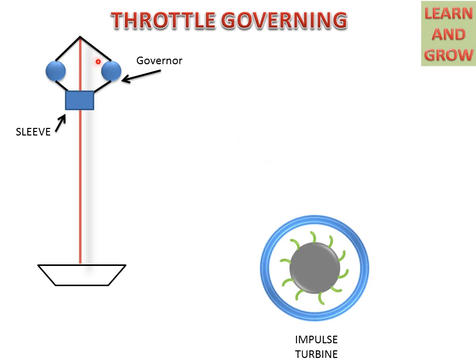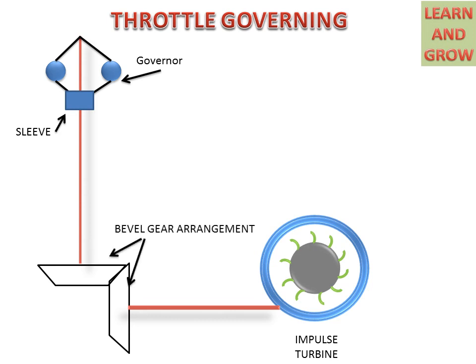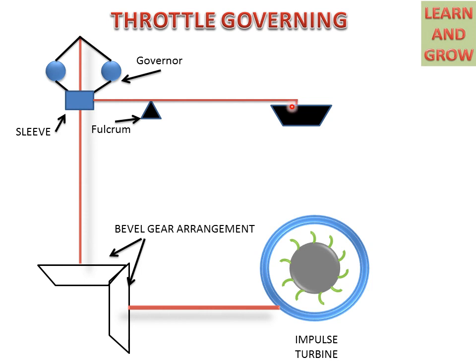The governor is connected with a shaft, and at the end of the shaft a bevel gear is connected. The turbine is also connected with a shaft and a bevel gear. This is the bevel gear arrangement for Throttle Governing. One end of the sleeve is connected to the valve. This is the fulcrum for the lever, and this is the main valve from which water will come and strike on the impulse turbine.